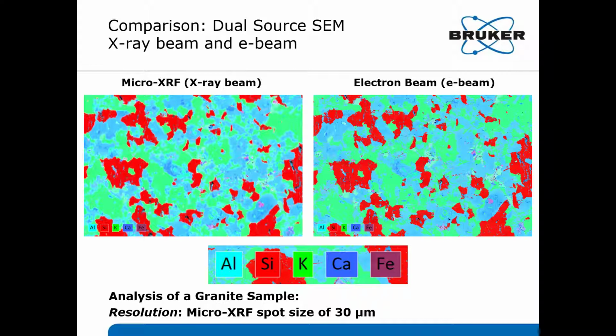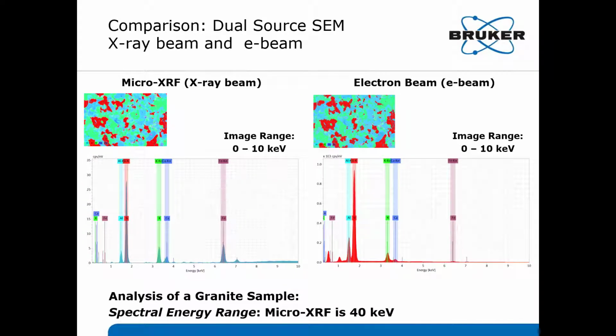The micro-XRF has a spot size of around 30 microns. However, there are some important differences between the two hypermaps. Firstly, the micro-XRF has a different excitation range and signal intensity to the E-beam. Here we see the total spectrum for the micro-XRF in blue on the left and for the E-beam in red on the right. Thus, whilst the major elements in the sample, e.g.